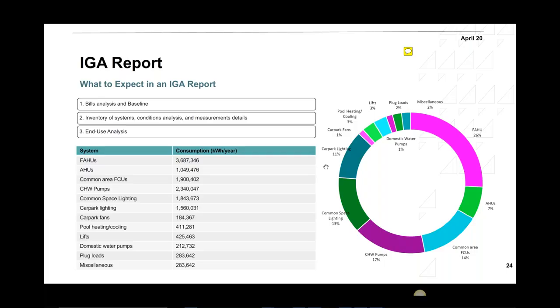So the right answer, like most of you have answered, is looking at the AC and ventilation fans. If you look at that, it's almost maybe more than 50% of the energy consumption of the building. So that would be a great area to look at. Now, this particular building, this is mainly the common area consumption, so that does not include the apartments. And it's on district cooling. This is why we don't see the chillers like we mentioned before. So yes, looking at the FAHUs, air handling units, common area FCUs, that would be a good thing to look at.